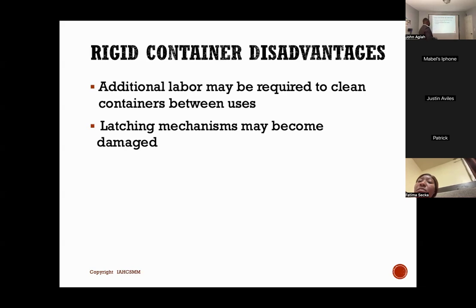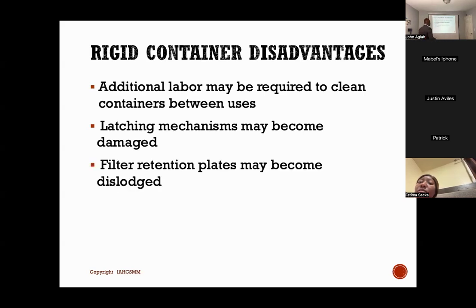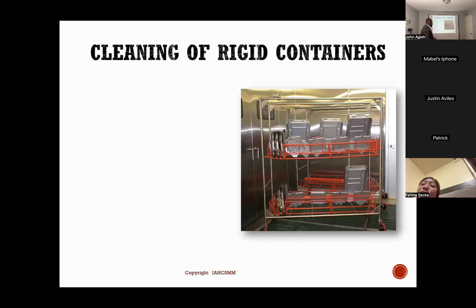Latching mechanism may become damaged. The latching is the locking, okay? The locking mechanism may become damaged. Filter retention plate may become dislodged. The filter retention plate is what I showed you. Sometimes, you did everything right, but then when it gets to the OR, they will see the filter drop inside the tray. In that sense, nobody will tell you that tray is compromised. Okay, so these are some of the challenges that we may incur.